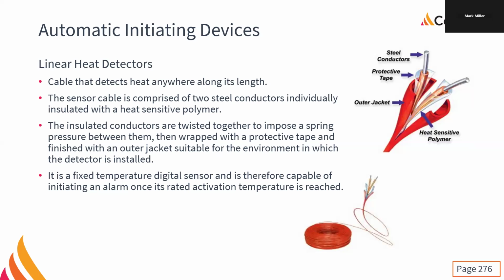But on the conductors, there's the protective tape and all that, but that's a heat sensitive polymer. If you heat up the cable, that polymer gets a little bit melty, and because the steel conductors are under spring tension, they'll touch and it'll set off the alarm. When it cools back down, it sorts itself out. It's pretty cool. If you put it under too much heat, yeah, it's going to fail. You might have to cut out and replace a section, but it works really, really well.